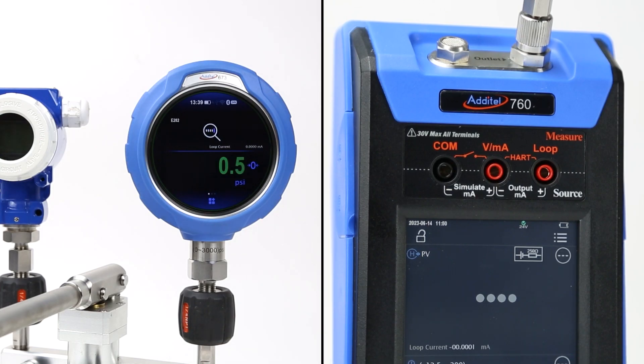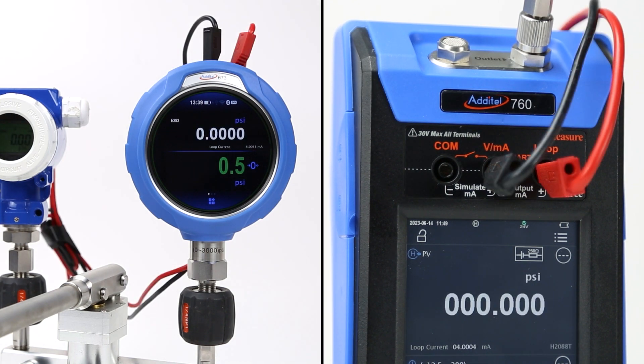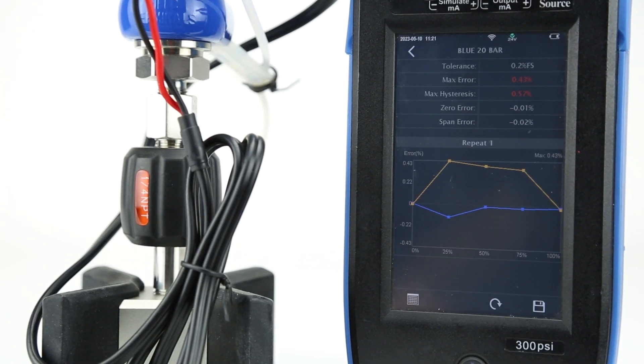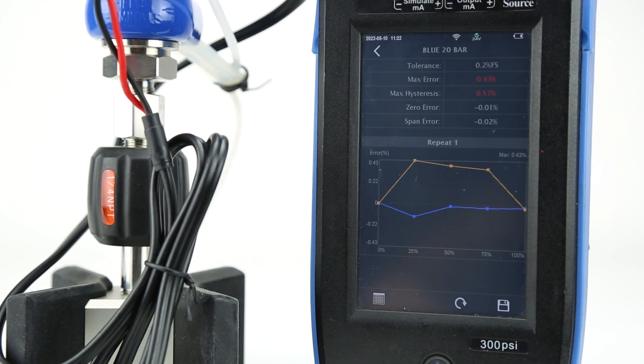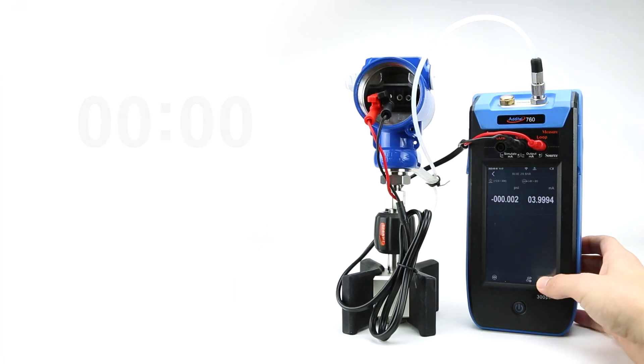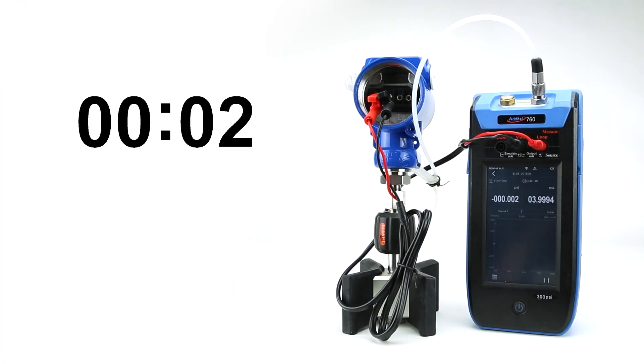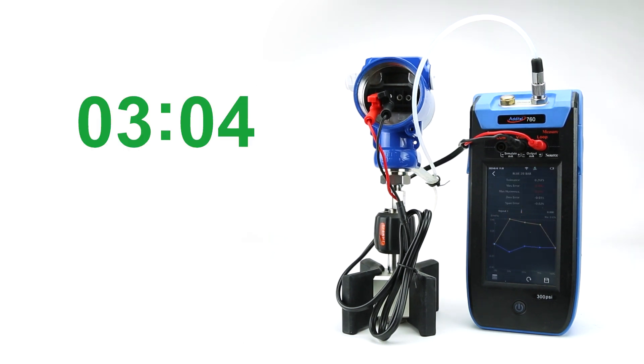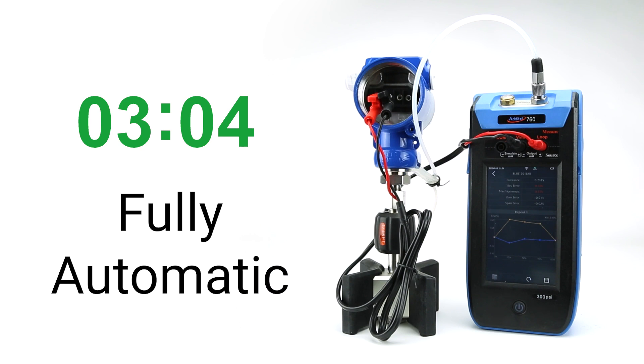In the case of a pressure transmitter, just connect the leads to the Additel calibrators, both of which can provide 24-volt power and utilize HART communication. Since the 760 generates its own pressure, while reading both its own reference module and the pressure transmitter signal, it can complete the calibration completely automatically, with no input needed after starting the test.